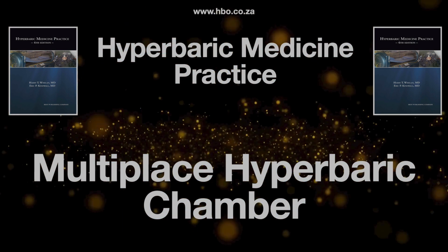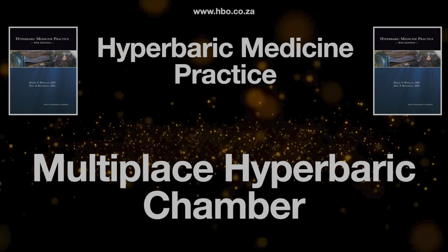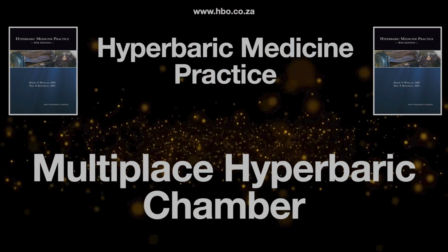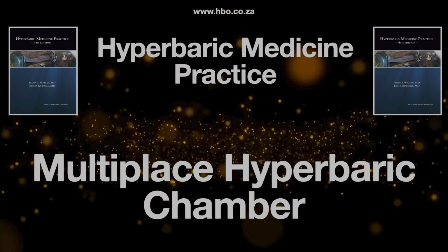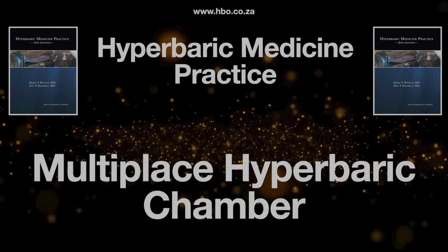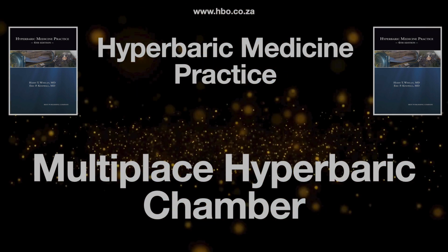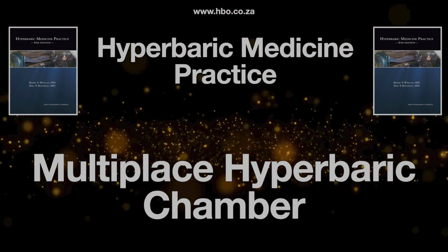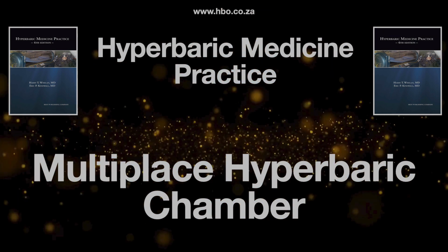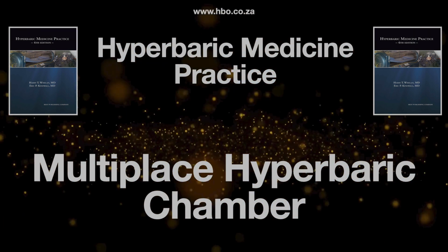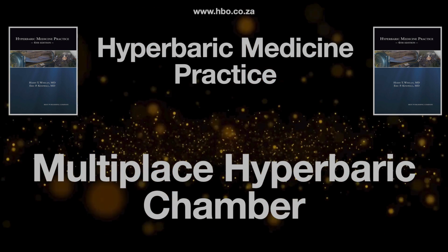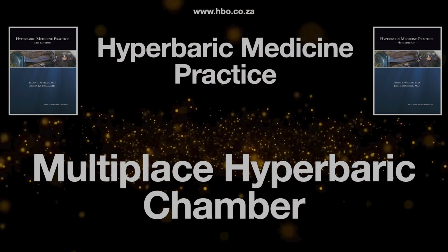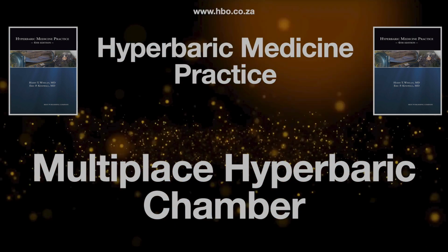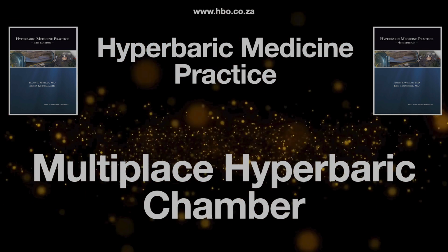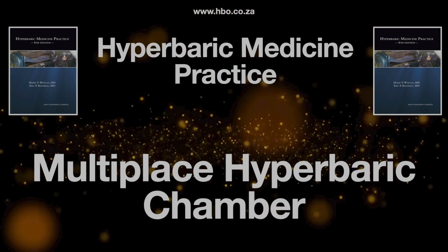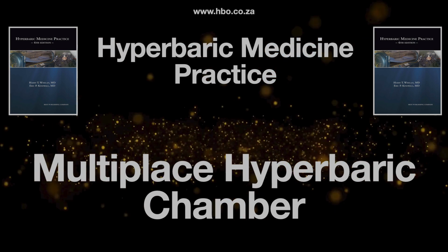Okay, so the construction is clearly incredibly complex. Huge emphasis on safety, redundancy. Let's shift to how they actually get pressurized. How does that work? This is another really key safety difference, especially compared to single-person or monoplace chambers. How so? Multiplace chambers are pressurized using compressed air. Just regular air, basically, but compressed, not pure oxygen. That seems like a huge safety advantage right there. Reduces the fire risk inside the main chamber itself. Massively. That's exactly why.